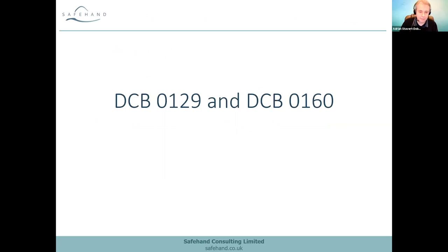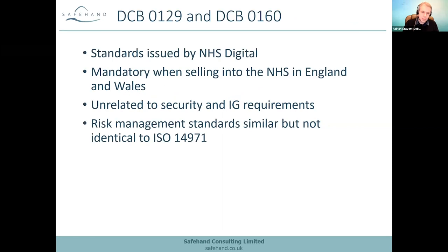So I'm going to talk a little more now about DCB 129 and 160. These might be standards you're less familiar with, hence me bringing this out on the call. These two standards are not produced by the EU or the MHRA — they're produced by NHS Digital. Compliance with them is mandatory if you're selling into the NHS in England and Wales. Outside of the UK, no one has ever even heard of these standards, so if you're dealing exclusively with Europe and the US, no one will have heard of them. But if you're selling into the UK, they are mandatory. Strangely, they're not enforced in Scotland and Northern Ireland.